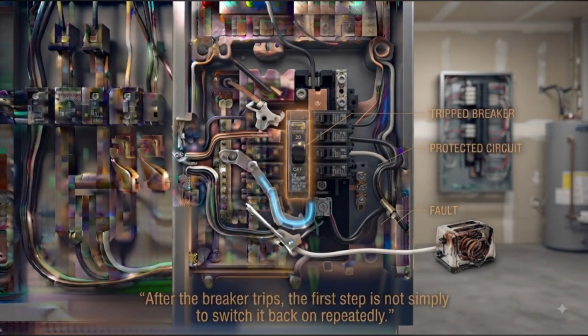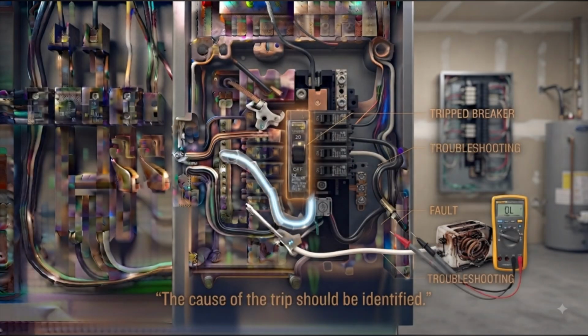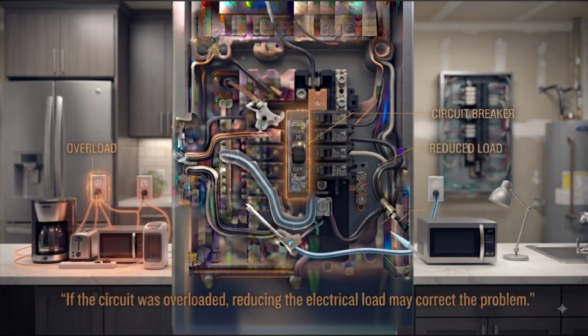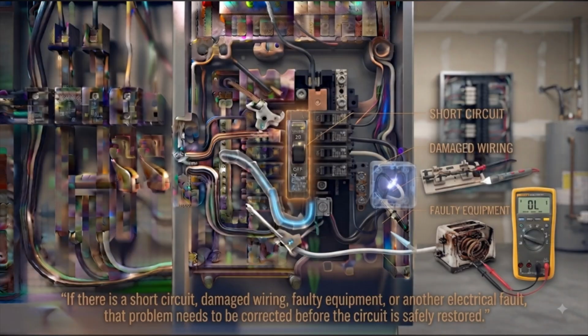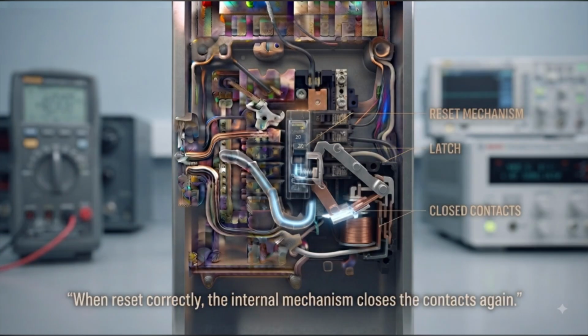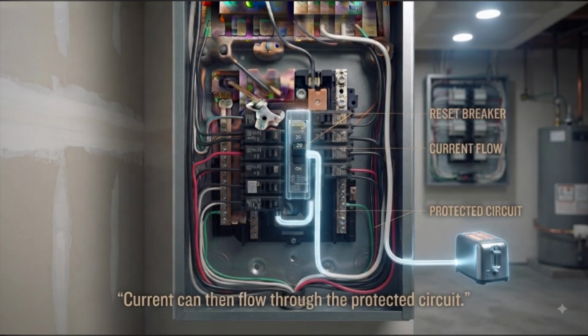After the breaker trips, the first step is not simply to switch it back on repeatedly. The cause of the trip should be identified. If the circuit was overloaded, reducing the electrical load may correct the problem. If there is a short circuit, damaged wiring, faulty equipment, or another electrical fault, that problem needs to be corrected before the circuit is safely restored. Once the fault has been addressed, the breaker can usually be reset according to its design and the manufacturer's instructions. When reset correctly, the internal mechanism closes the contacts again. Current can then flow through the protected circuit.